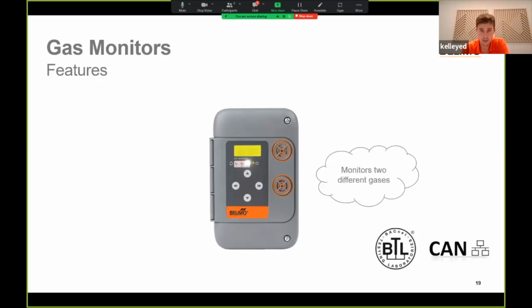First, each device can monitor up to two different gases. The sensor modules, which is the part in the gas monitor that physically senses the gas, are hot swappable and factory calibrated. So when you replace them, you don't need to disconnect power from the device, and you don't need to recalibrate them after you install. Second, they have analog outputs and relays that allow for direct control. And third, they have CAN bus and BACnet MSTP for communication that allows them to be used as a standalone system or integrated into a BMS.